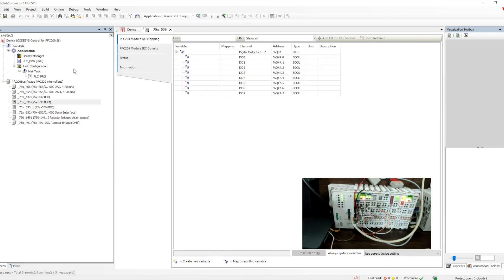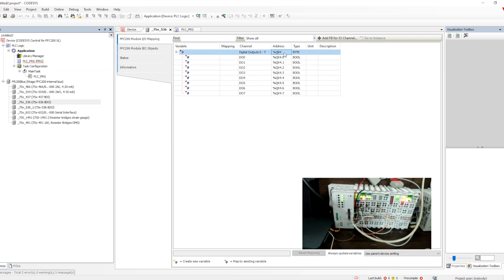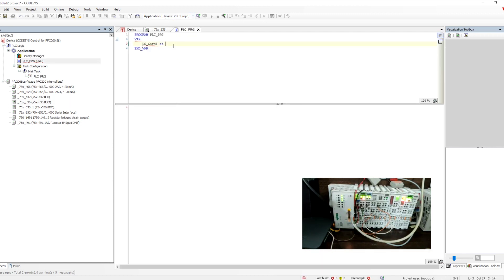The IO channels will not be communicating because they are not yet used. This is true for any hardware — with Codesys runtime, until and unless the IO channels are utilized, they will not be scanned. That is a default feature. In order to scan or use any IO channel, we have to assign a variable and use that variable in the program.